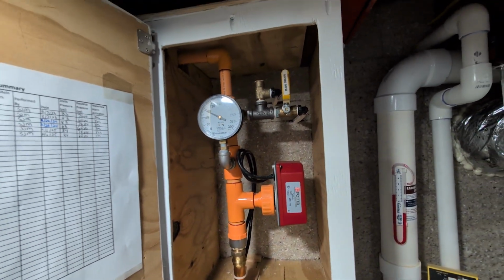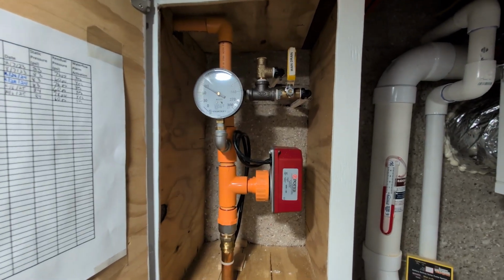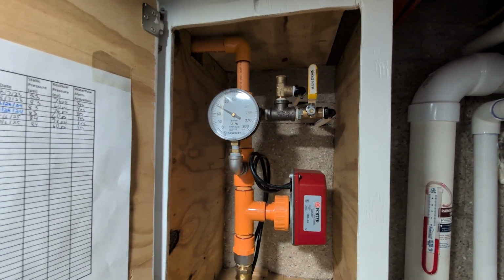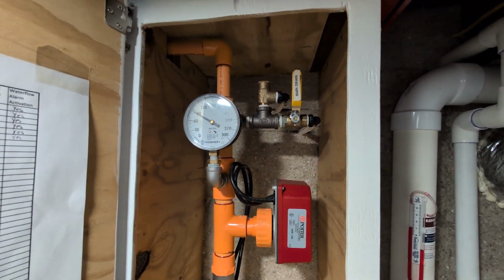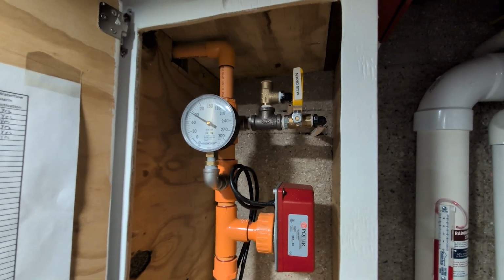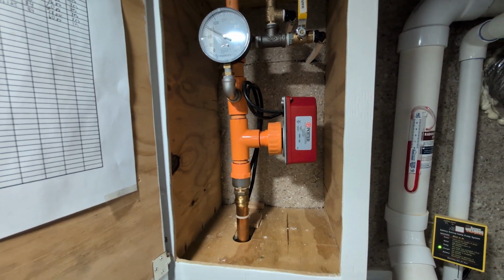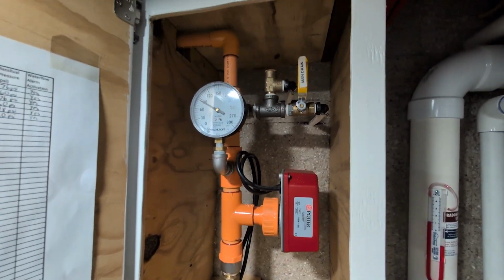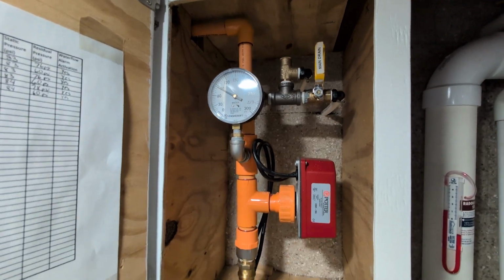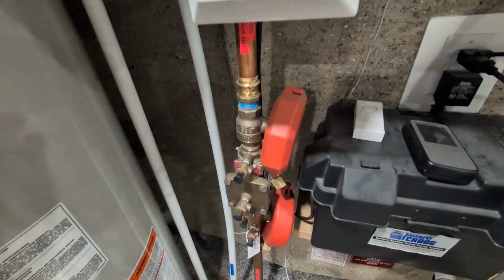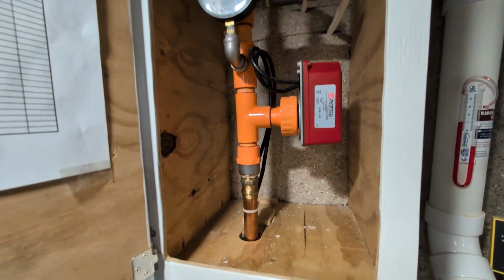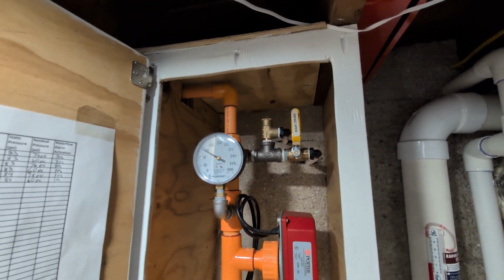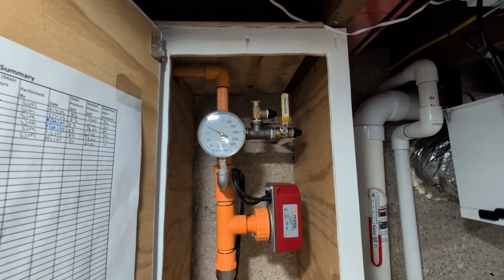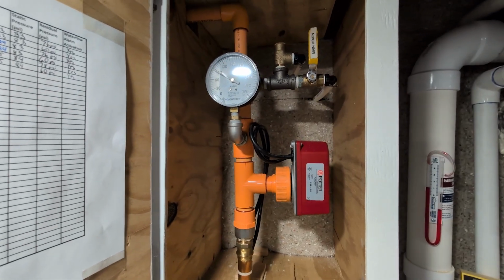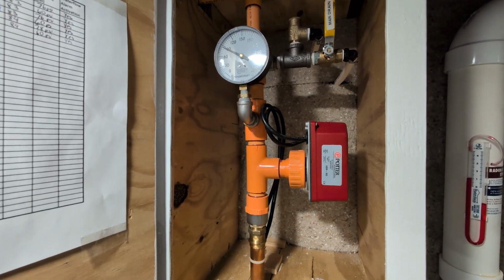You can also utilize a tank and a pump. And what's different about that than, say, an NFPA 13 system is the tank and the pump don't have to be listed. Also, we're only looking for a water supply that's either 10, sometimes as low as 7 minutes, because again, we're just trying to give time for those occupants to get out prior to flashover. So given the lower flow rates of these types of systems, as well as that limited time, the tank might be as small as 250 gallons. So that's a pretty small water tank that we're talking about in that basement. And also, you can use wells for supplying that water, so that is an option as well.